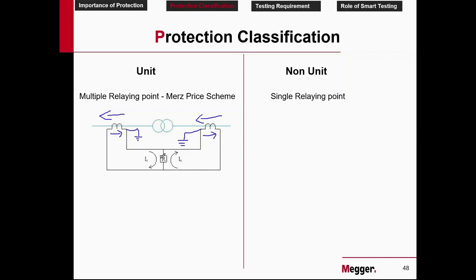And this is the relay. So that means what? In the relay, the current is opposing each other. Current flows in the opposite direction. So let us say both are having a CT secondary ratio of 1 amps. That means your full load current is 1 amps. So 1 amps flowing here, 1 amps flowing here. 1 minus 1 will be your differential current, that is 0. When there is no fault, the current will be 0. That's what is read by the relay.